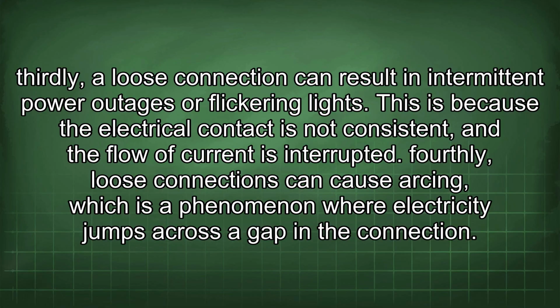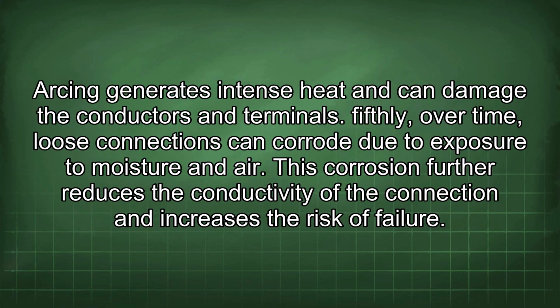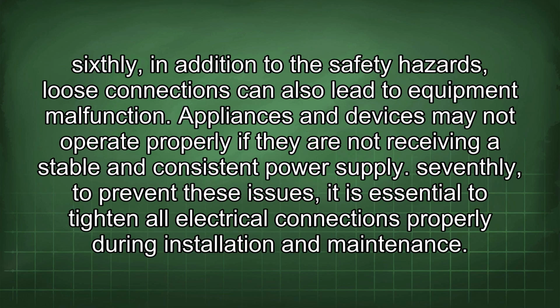Fourthly, loose connections can cause arcing, which is a phenomenon where electricity jumps across the gap in the connection. Arcing generates intense heat and can damage the conductors and terminals. Fifthly, over time, loose connections can corrode due to exposure to moisture and air. This corrosion further reduces the conductivity of the connection and increases the risk of failure. Sixthly, in addition to the safety hazards, loose connections can also lead to equipment malfunction. Appliances and devices may not operate properly if they are not receiving a stable and consistent power supply.